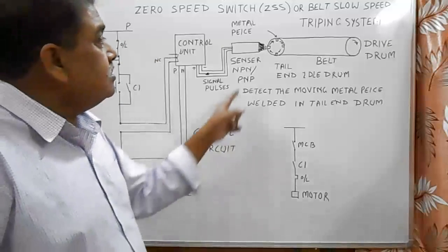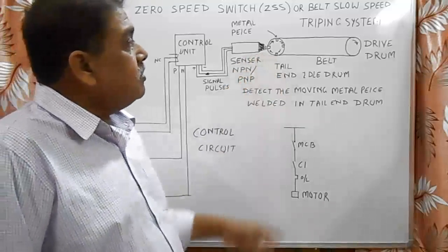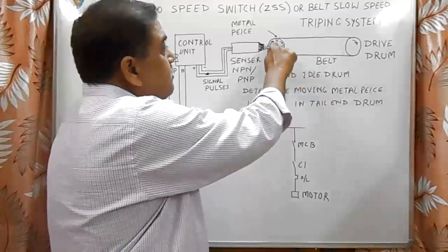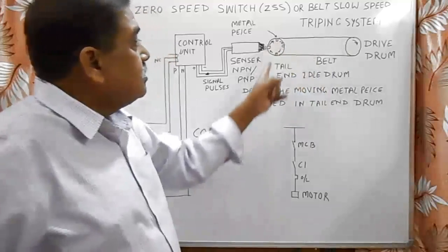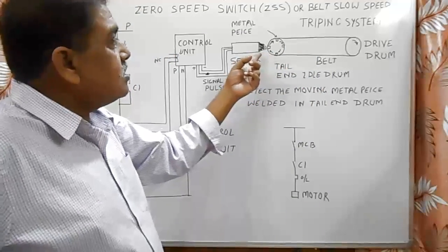Here we use a sensor with the tail end drum. When the belt moves with a certain speed, these metal pieces are welded to the tail end drum that rotates in front of the sensor, so the sensor generates continuous pulses at a particular frequency.